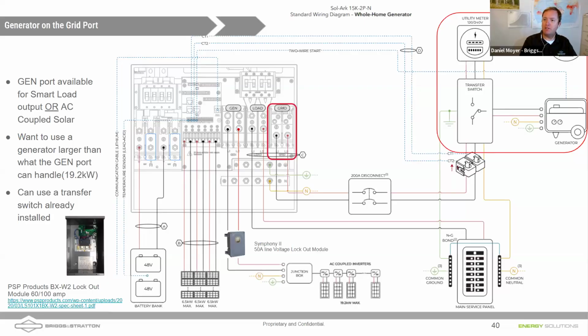So what we need to do now is have a physical disconnect to prevent those AC coupled microinverters or string inverters from backfeeding the generator. Yeah, we don't want the power of those AC microinverters going into the alternator, the generator, right? If the generator is running and there's not much power being drawn by the loads of the house and the AC coupled solar is feeding back in, they could backfeed the generator and ruin the generator. So by installing a $100 Symphony 2 line voltage module, we can turn off that solar whenever that generator is powered up.